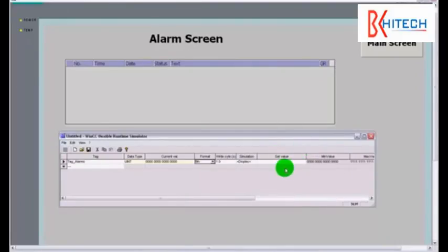Now, one thing, don't get too confused with this: notice that in the minimum value, maximum value and the current value, they've got them in blocks of 4 bits and there's a space between them. What we're going to do is simulate the value and put the value in ourselves, but we must put the value in without spaces. Okay, now remembering that this bit is our DB2.DBX 0.0.